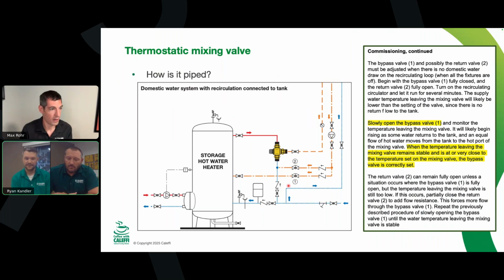So if you're looking for 113 degrees out and you start to adjust it, and with the recirc pump running for 5-10 minutes it's still 120, 125, you haven't adjusted it right. You want to open it so that you see that 113 stabilize—that's basically our goal here.